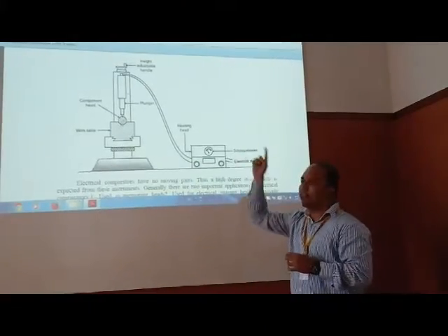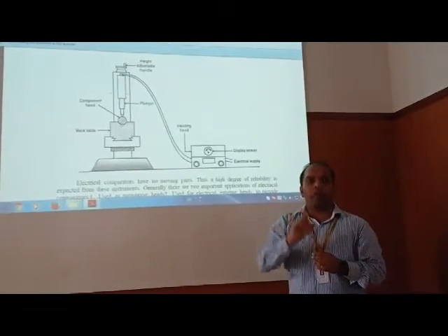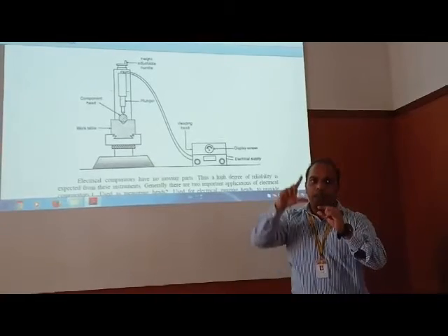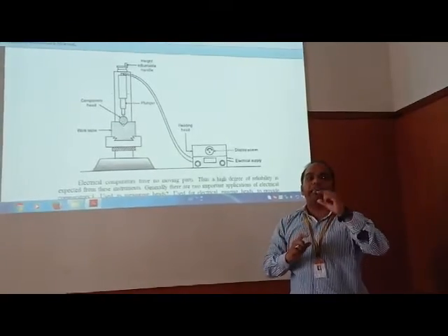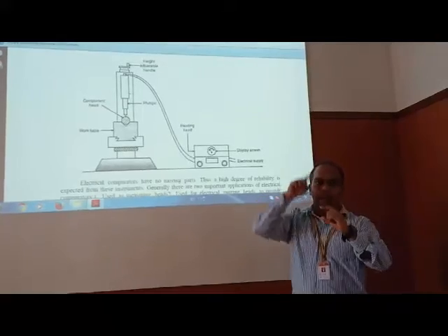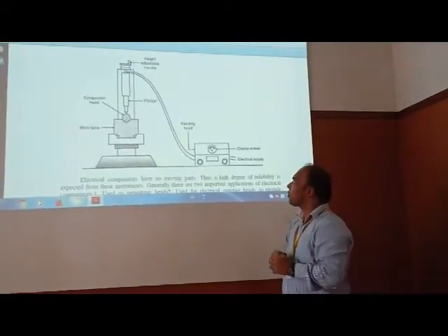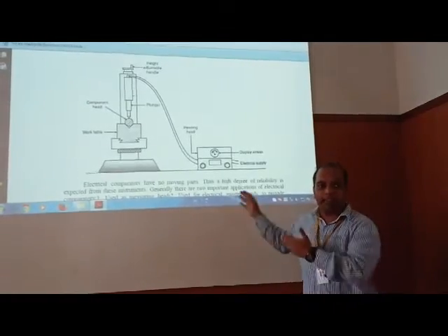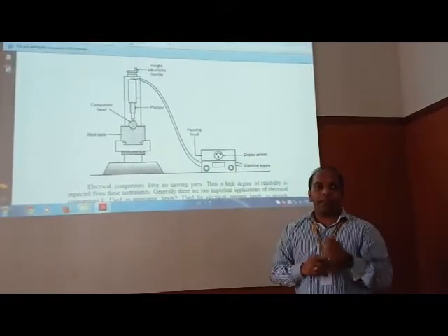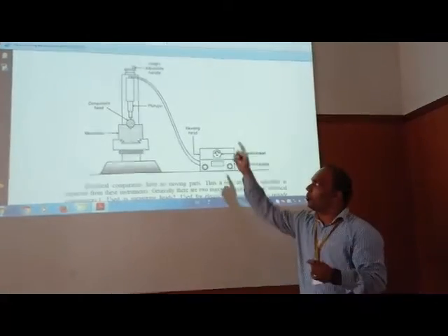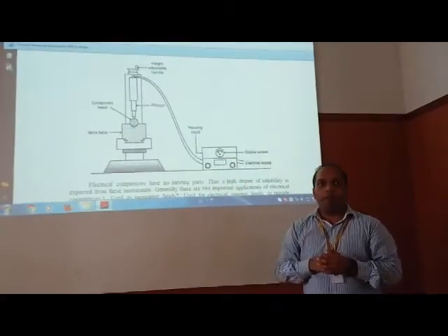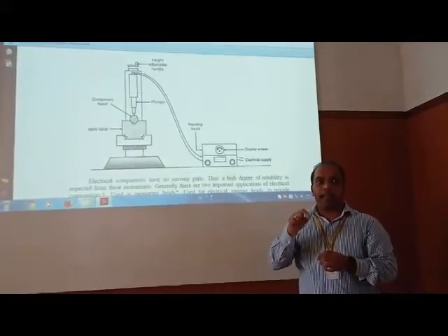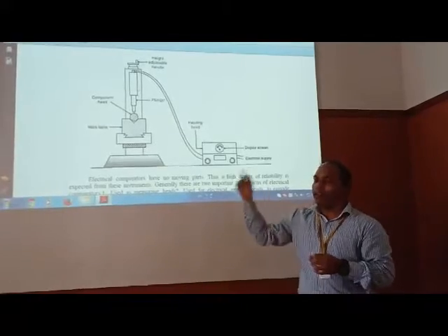The height adjustable handle will give us a small relief as per the workpiece dimensions. If it is smaller, we can lower the plunger. If it is bigger, we can raise the height adjustment. Now, the point of working, how working occurs, let's see. The electrical supply will give an electrical signal to the plunger through this connection. The plunger will be moving in the y plus and y minus direction as per the signal, and vice versa.